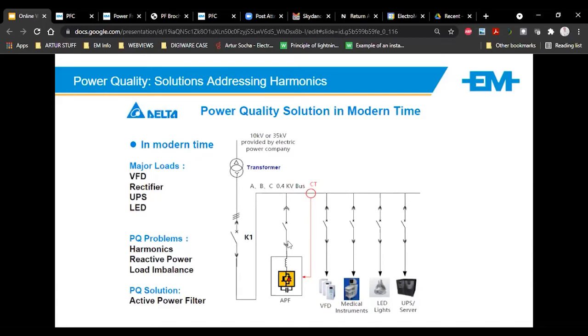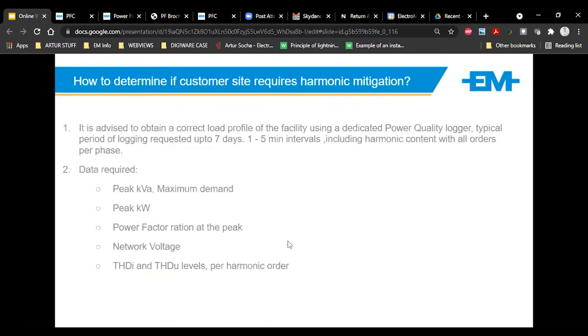Inherently, yes, it's clean power, but quite often there will be noise and they will say, if you exceed a certain percentage, you have to clean it out before you give it to me. And the only way to do that would be with active power filters. Okay. How do we know if a customer needs it? Again, we need a load profile, a dedicated logger with power quality logging in. And based on all that, again, kVA, kilowatt, power factor, network voltage and current harmonics per order, to be able to determine the size of filters you may need, or you can get away with no filters. You just need to put line reactors on your PF system and so forth.